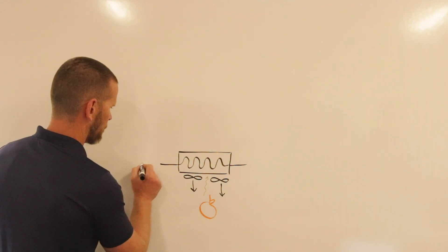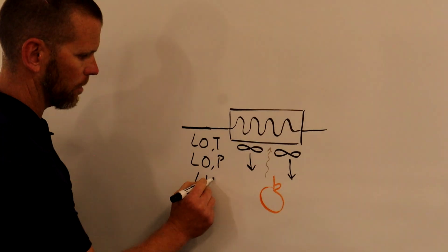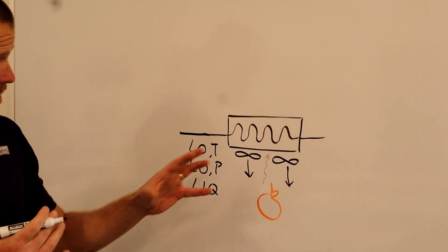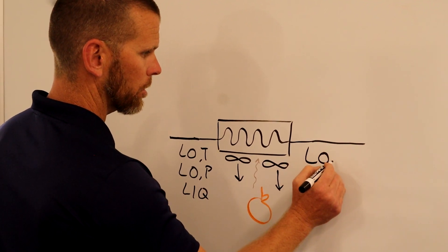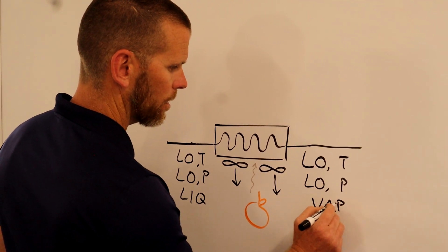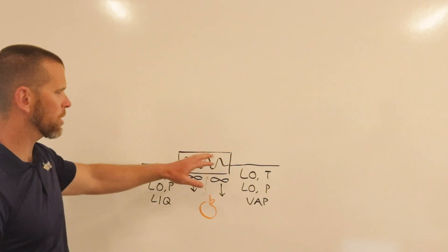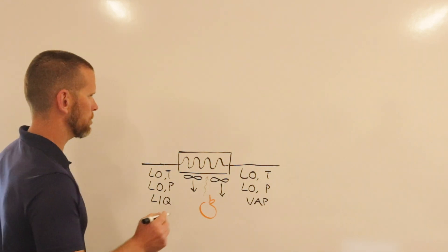The ammonia enters the evaporator as a low temperature, low pressure liquid. Because of heat added to the evaporator from the orange, it exits the evaporator still at low temperature and low pressure, but now as vapor. When a substance changes from liquid to vapor, there is no change in temperature. Technically there is a pressure drop through the evaporator, but it's minimal and designed to be minimized, so we can say it occurs at constant pressure. From the evaporator, what do we do with this low pressure vapor? We need to recompress it.